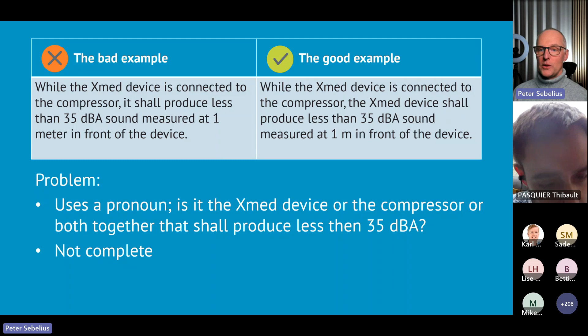Keep in mind, if you're writing a short story or a novel or something, or just an email, you would want to use it because you don't want to regurgitate the words and terms over and over again. But here you need to think of requirements more as if you're writing software code. It's perfectly okay to repeat yourself to make it accurate. So the right solution would be to say, while the XMED device is connected to the compressor, the XMED device shall produce less than 35 dBA sound measured at 1 meter in front of the device. So this requirement was actually not complete the way it was from the beginning.